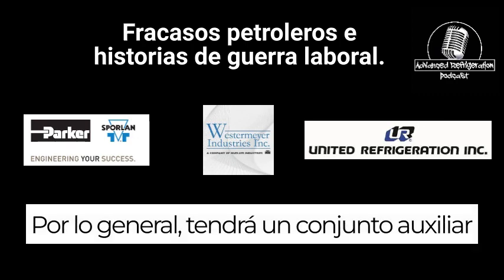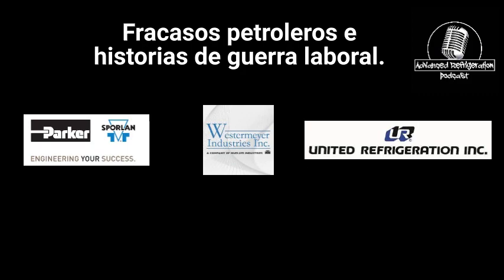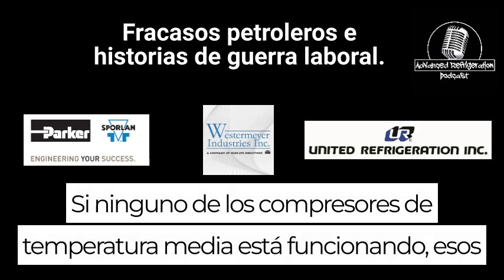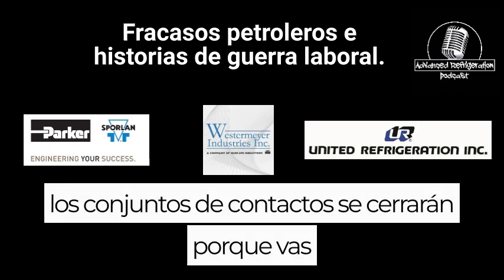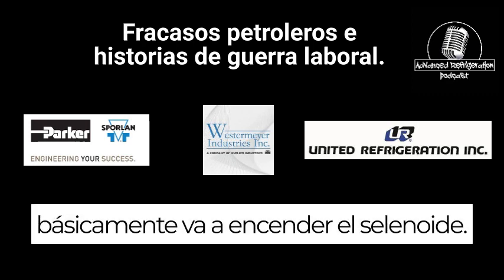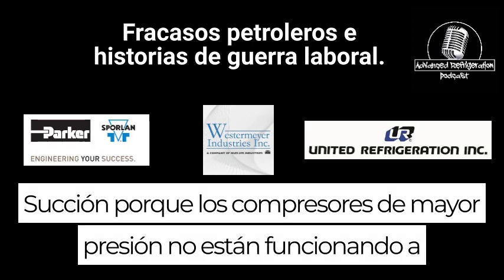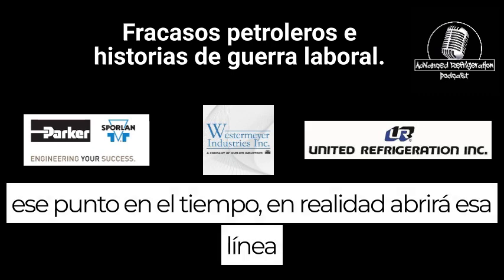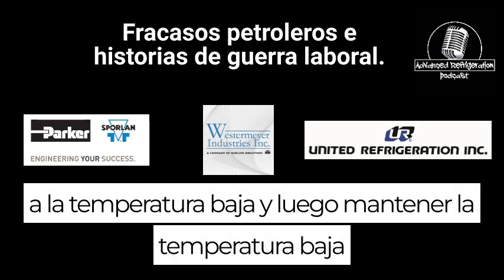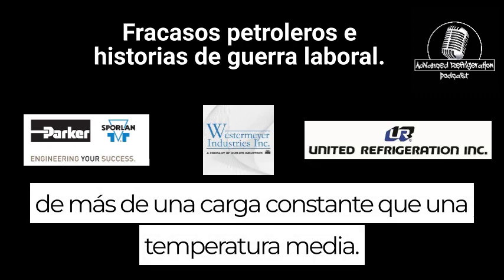typically you will have an auxiliary set of contacts on your medium temp compressors. If none of the medium temp compressors are running, those sets of contacts will be closed, because you're going to wire them up normally closed. And then it's basically going to power up the solenoid. So instead of the OCV going to the highest suction, because the highest pressure compressors are not running at that point in time, it'll actually open up that line to the low temp and keep the low temp compressors running. Because usually the low temp header has more of a constant load than a medium temp.